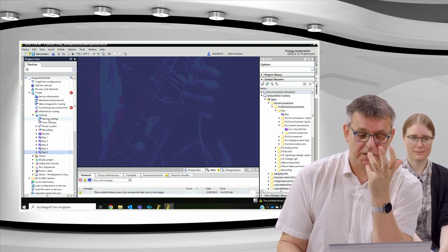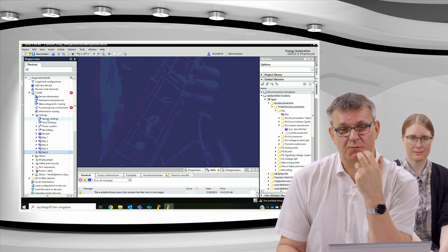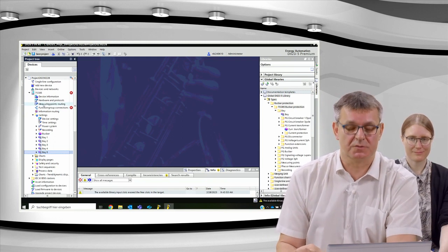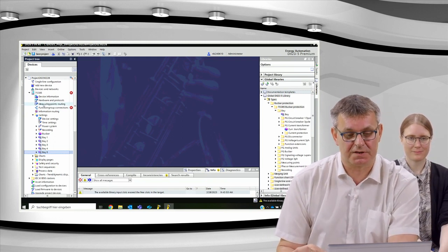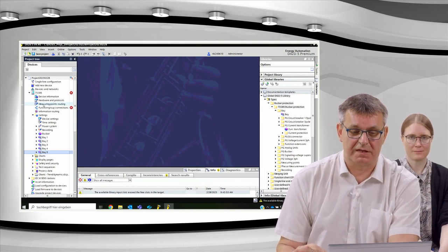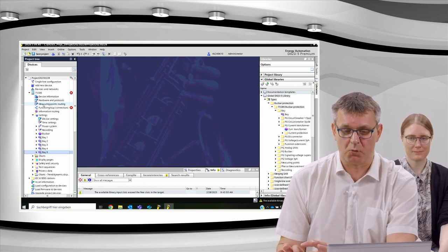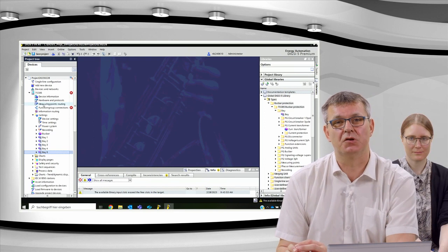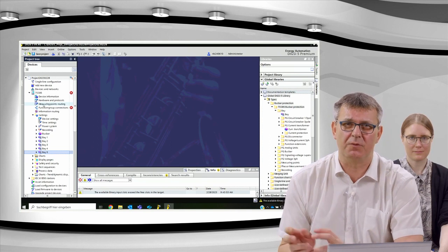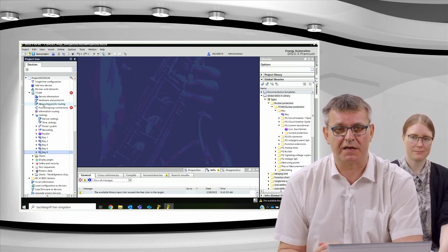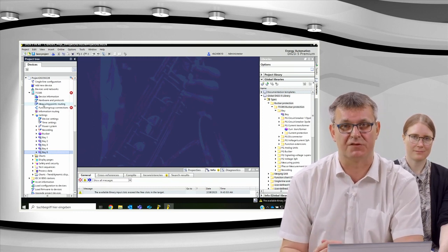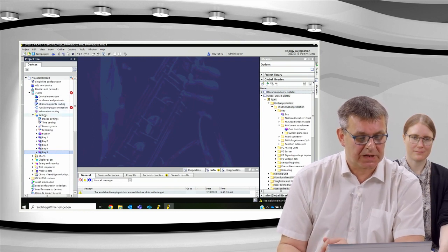And now maybe you may be confused as we have not been asked whether the routing of the binary inputs and binary outputs should be copied. The reason is that now there are not enough binary inputs and outputs available anymore. I decided, as a philosophy, not to copy it partly, because then you have to see anyway which should be copied and which not. So I decided, okay, if there are not enough binary inputs and outputs, don't copy any of the routings. And this has been done. Let's have a look.